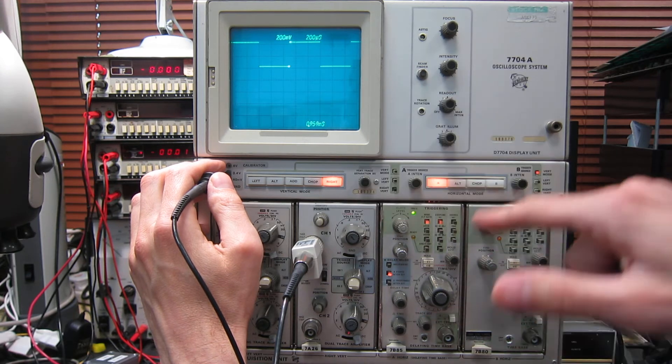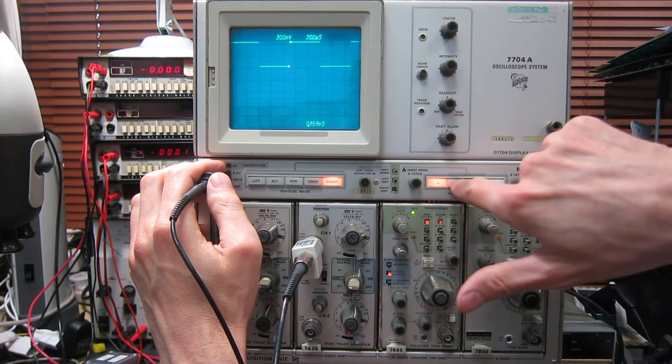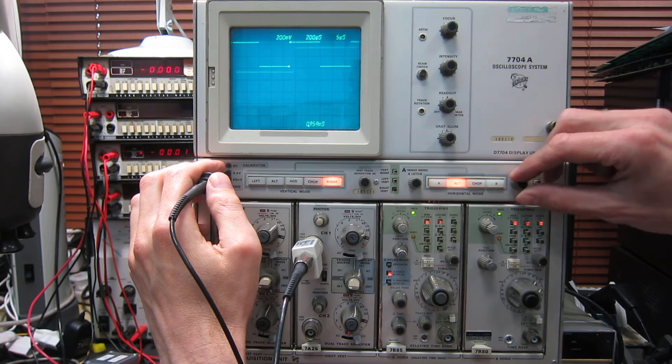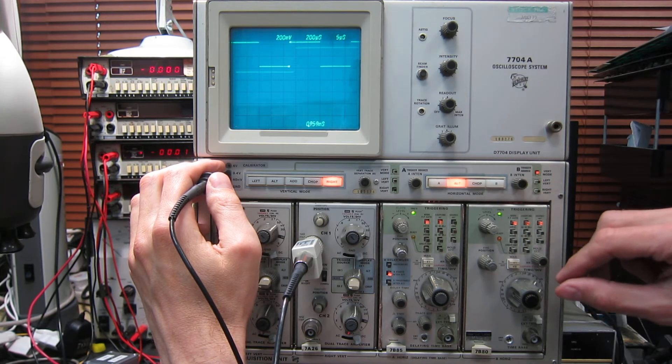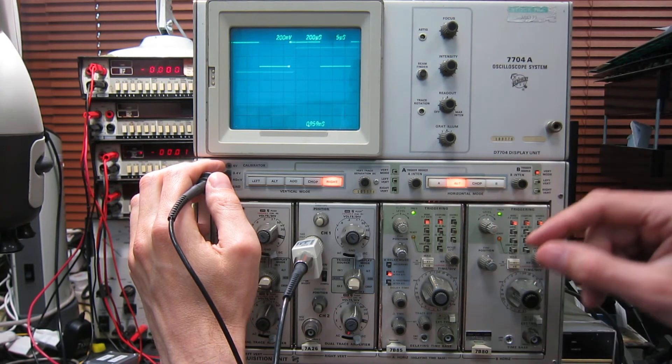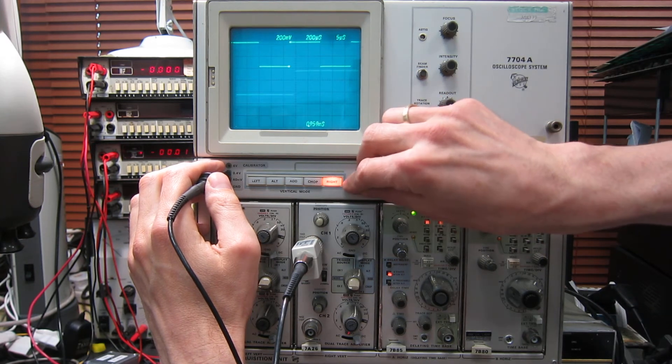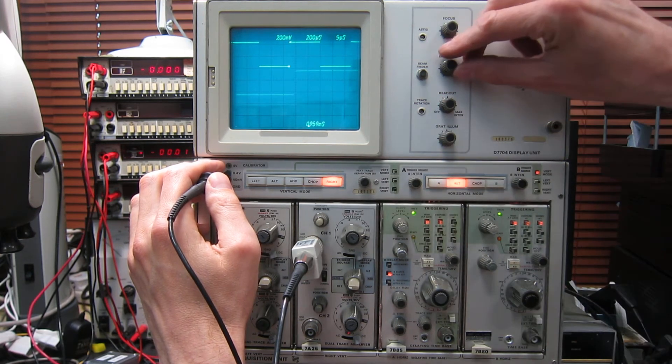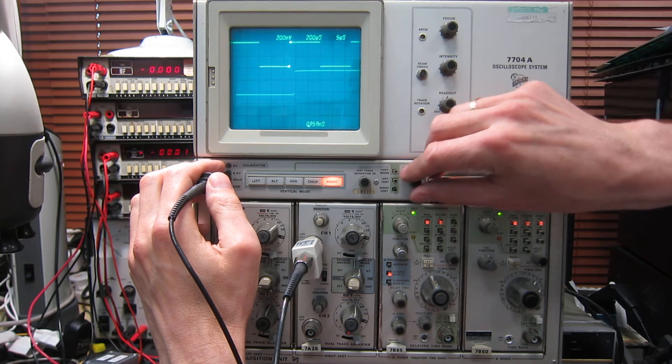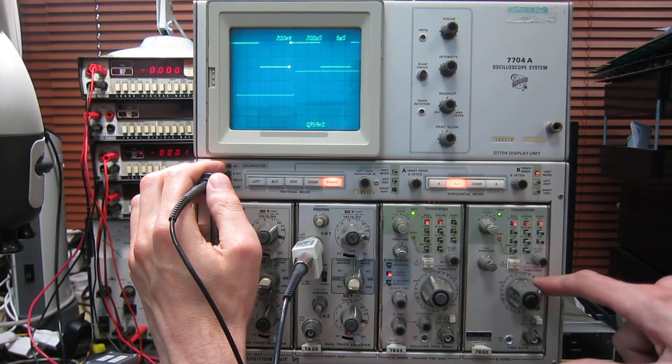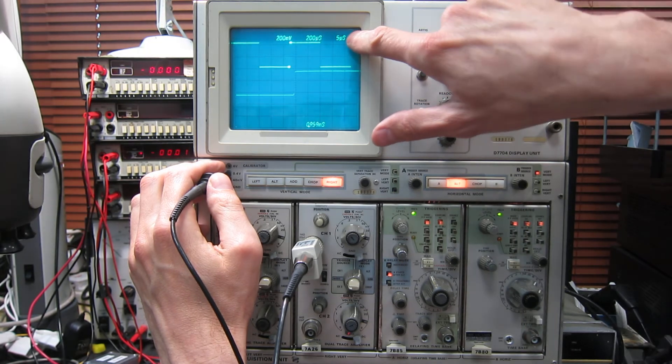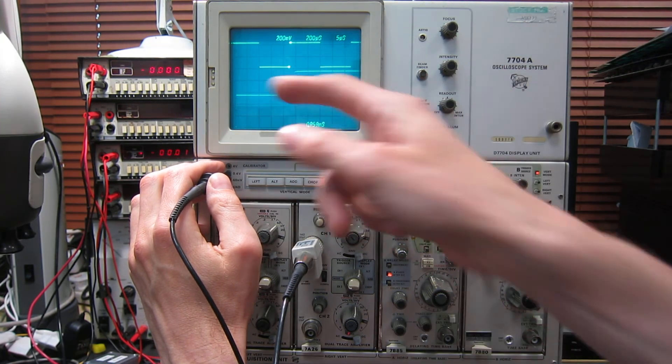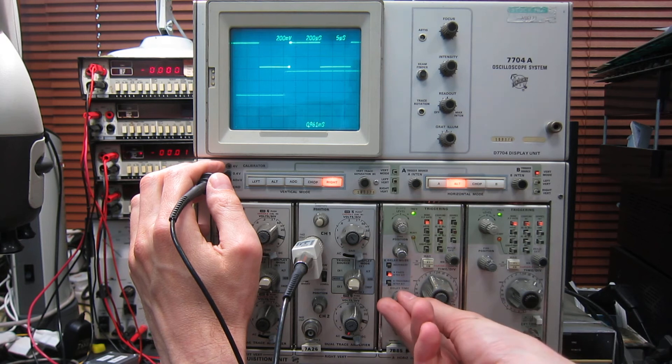Now, having highlighted that, I can put it into alternating mode, which displays the second time base at the same time. There's a trace separation. There we go. Let me turn that up and that down a bit. You should be able to see everything. So now we're seeing time base B, which is running at five microseconds per centimeter, but that starts when the delay expires on time base A.